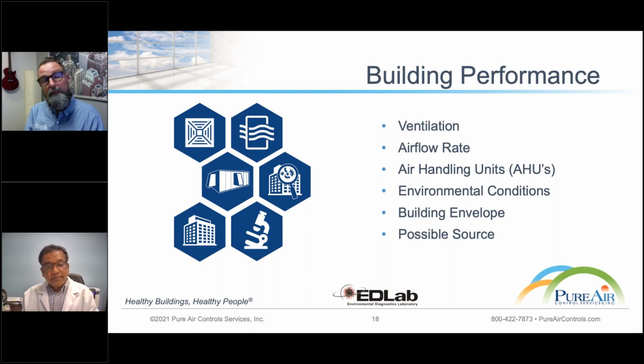But if you go into a hospital or other facility where the air needs to be circulated many times to thin out contaminants or their accumulation, it can go up to 8, 9, or 10 times. This is called ACH, air changes per hour - that's what we need to maintain. The air handler unit is the lungs of a building, so you have to think about what kind of air handler unit you have.